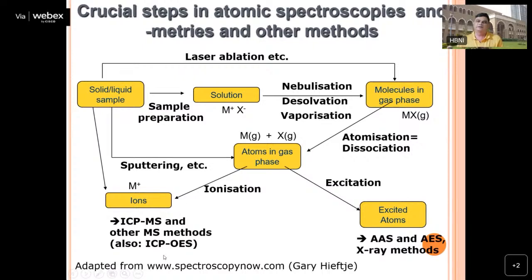Now we are getting detectors with resolution of less than about 4 picometers. So nowadays, whatever the ICP is, we can use both atom lines as well as ion lines. There are many ionic lines in emission spectroscopy which can be used. That's why the combined term is now ICP OES.